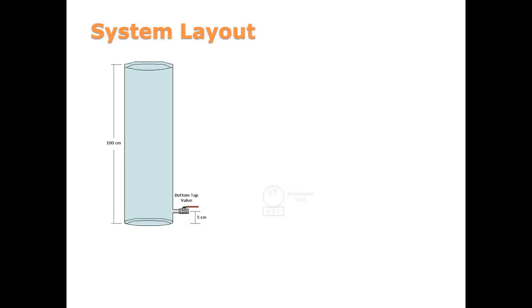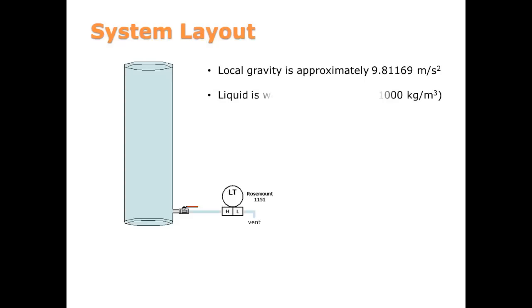The level transmitter is to be mounted at the same elevation as the bottom tap on the tank. The local gravity is approximately 9.81169 meters per second squared, and the liquid being measured is water at 4 degrees Celsius, which means the density is approximately 1,000 kilograms per cubic meter. You'll notice that the water used is probably not this cold, but to simplify the range calculation, this density will be used. There will be a small error in the level reading due to this assumption, but it should be negligible.